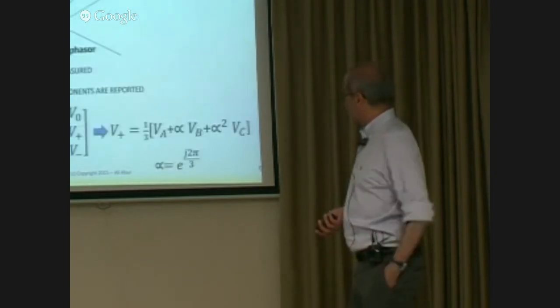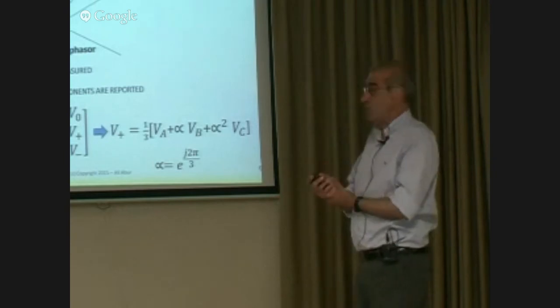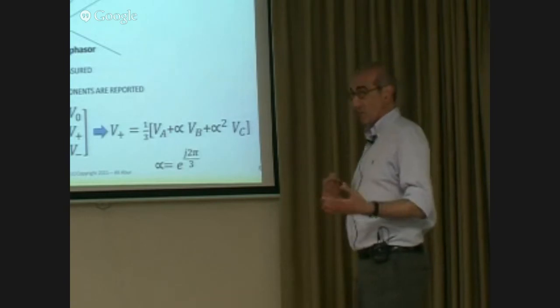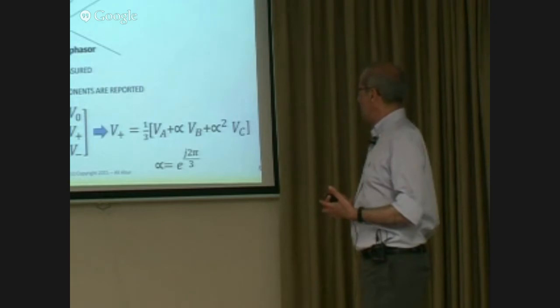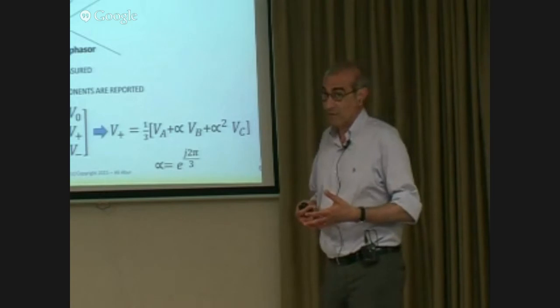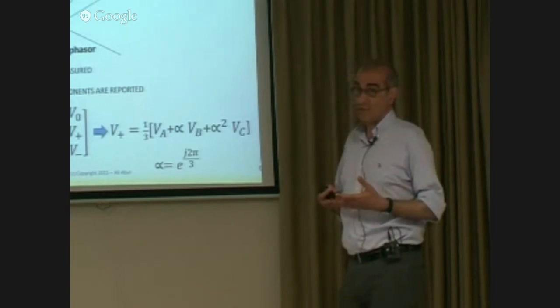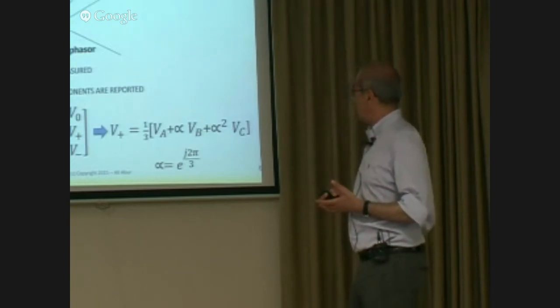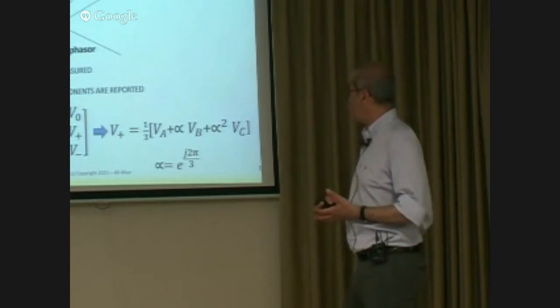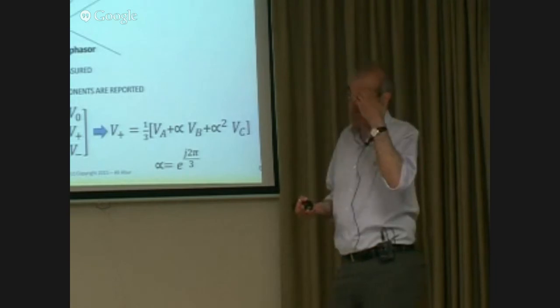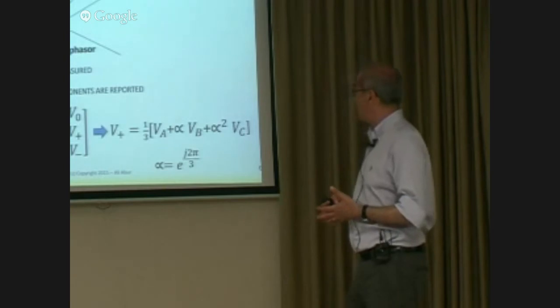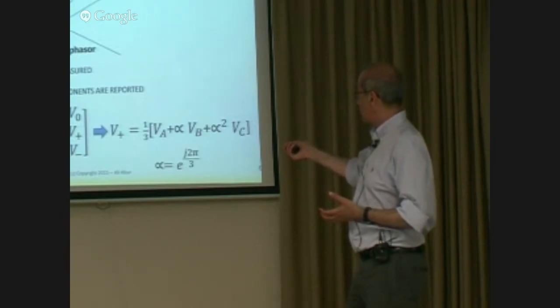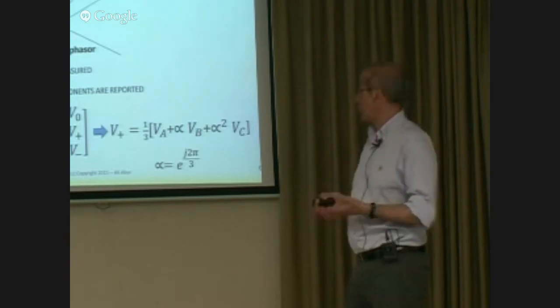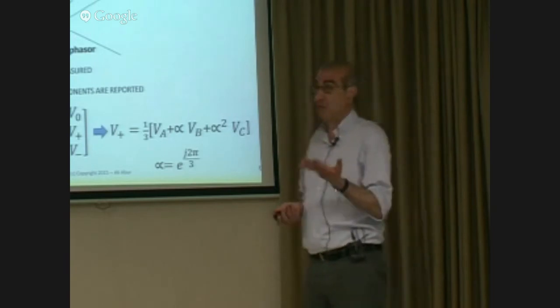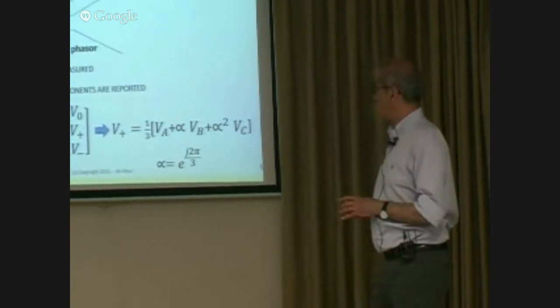The other thing is, depending on the type of PMU, we may be measuring voltages or currents, and of course these are all three-phase quantities. If you measure a voltage, you're actually measuring ABC phase voltages, and the same goes for currents. Depending on how many channels you have on the PMU, it may measure one set of three-phase voltages plus several sets of currents. In this particular example, we're showing all the lines coming out of this substation being measured as currents, plus the voltage at the substation. So this PMU can measure about 1, 2, 3, 4, 5 times 3 - 15 quantities altogether in individual phase currents and voltages.